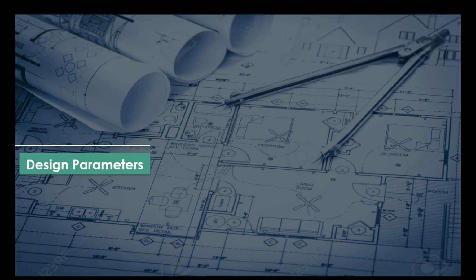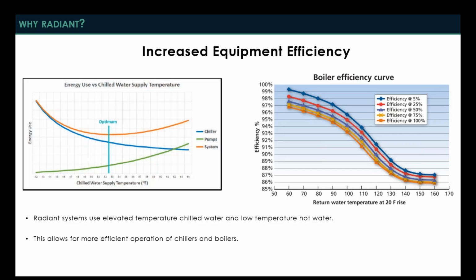So I'd like to dive into a little bit of the design parameters for radiant systems. And again, I tried to keep it high level. We could do a 4-hour or even an all-day presentation on the very specific design requirements for radiant systems. But I tried to keep it high level so that you can get the main ideas of what we're trying to accomplish. But it should be noted that these types of systems do require a little bit more design than maybe an all-air system might. So it's just something to keep in mind whenever you're moving forward with a radiant system, that there are a lot of calculations and things that need to be looked at to make sure that they're effective.